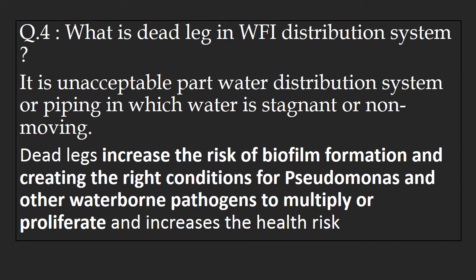Question number 4: What is a dead leg in a WFI distribution system? It is an unacceptable part of the WFI distribution system or piping in which water is stagnant or non-moving. Dead legs increase the risk of biofilm formation, creating the right conditions for Pseudomonas and other waterborne pathogens to multiply or proliferate, thereby increasing health risk.